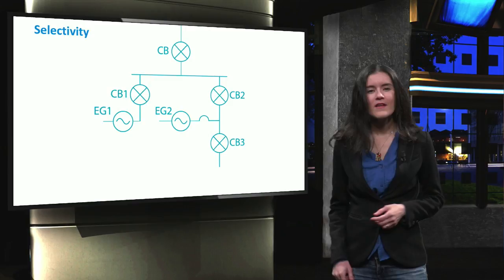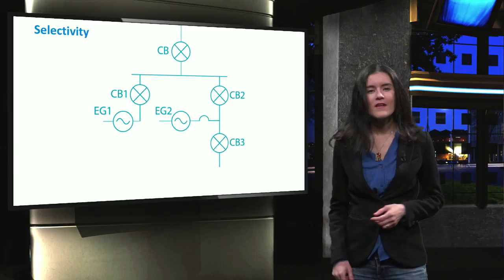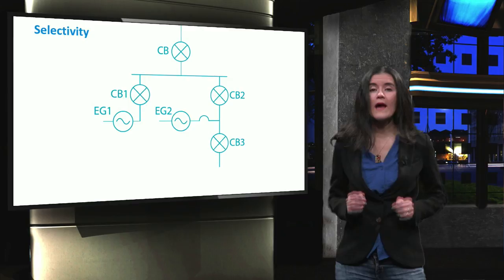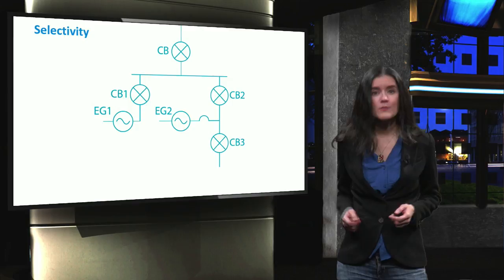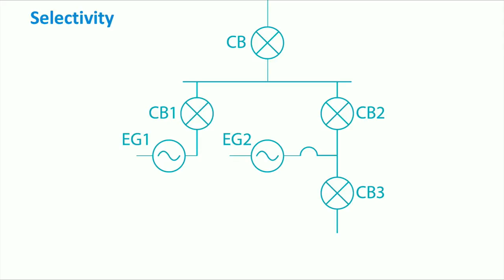The second criterion is selectivity. Once our protection devices are correctly tuned, we want the protection scheme to only isolate the faulted part of the grid. This must be ensured in order to minimize the possible negative impacts of the fault on the rest of the grid. In this example, a fault occurs in the lower part of the system. When the short circuit currents injected by the generators in the system start flowing, a correct operation would lead to the disconnection of circuit breaker number 3.